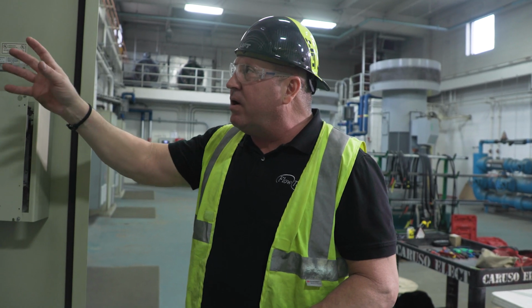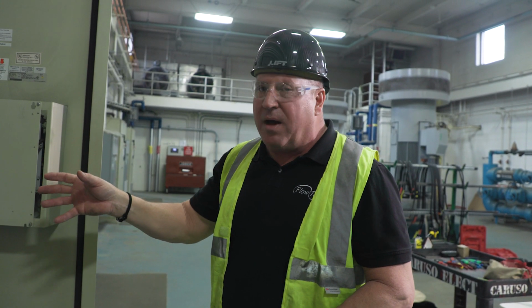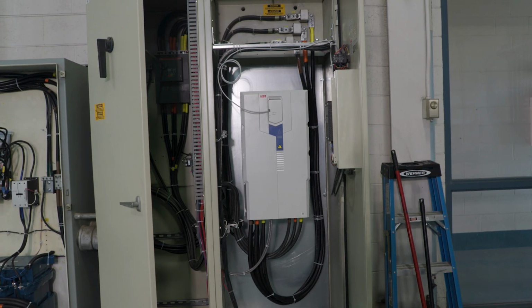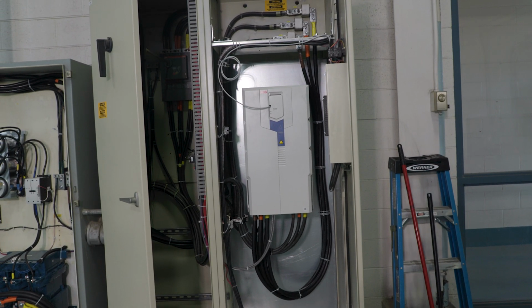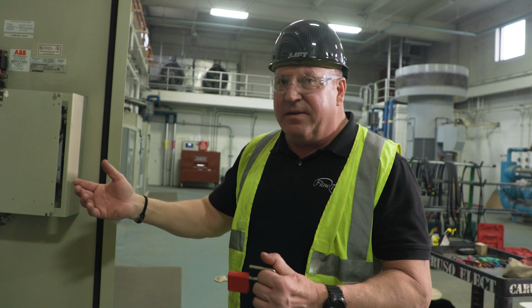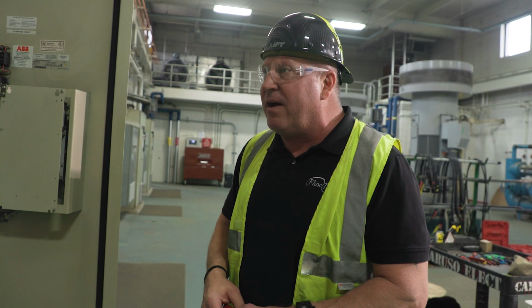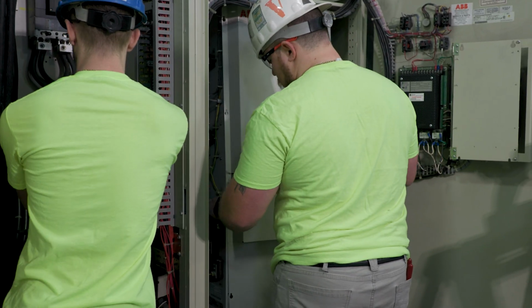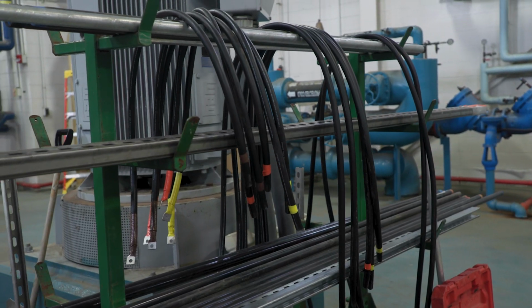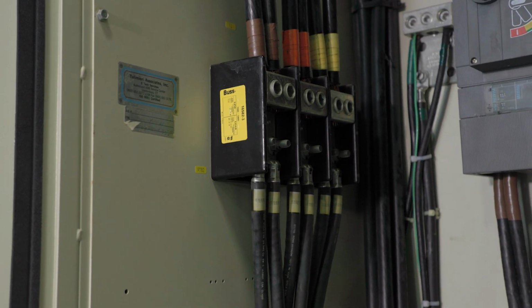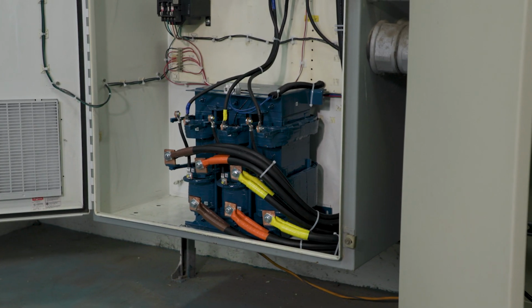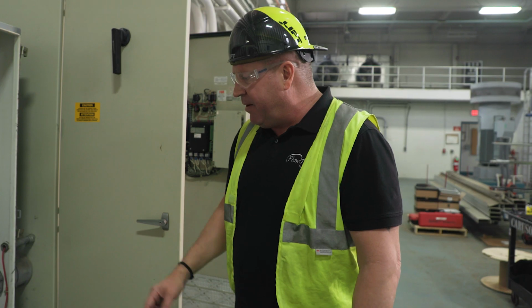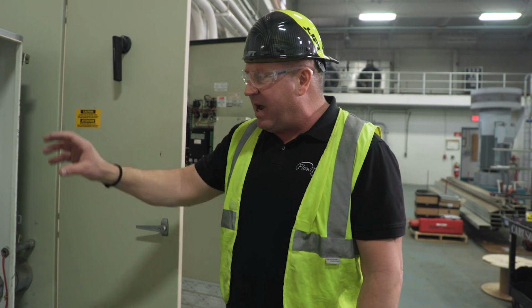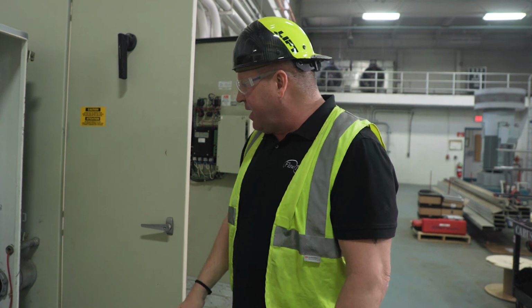We hang it with that hook. I leave the hook there, so if we ever have a problem, we have to re-pull it. You just re-hook to it, hook the drive, and it comes out. They're heavy, so we kind of think ahead on trouble that we may have. Once we put the panel and we get the drive in, then we'll start running the cables into the drive. Once we're gutted in the harmonic filter, we'll start reassembling, mounting blocks and the new cap bank and new reactor on the bottom.